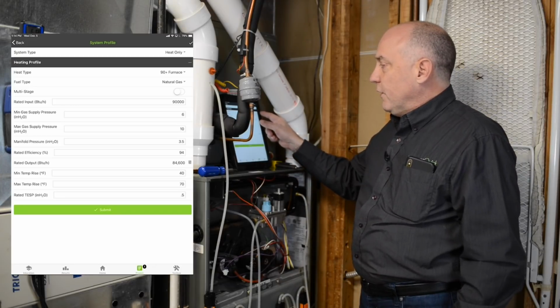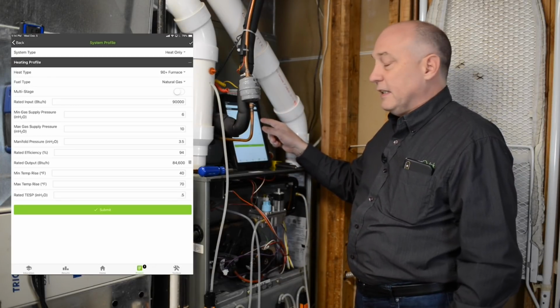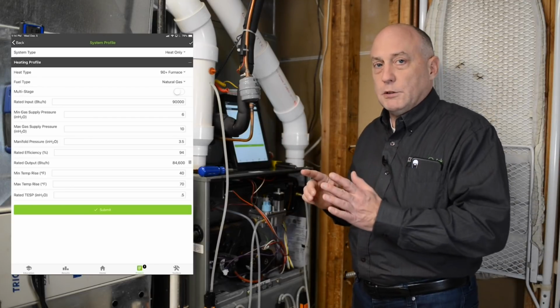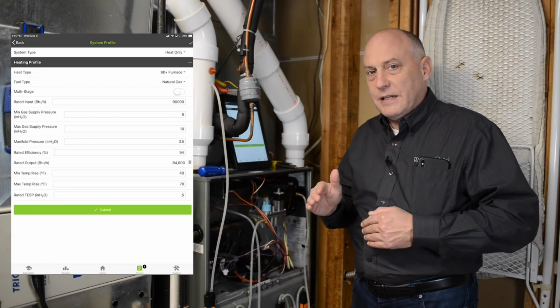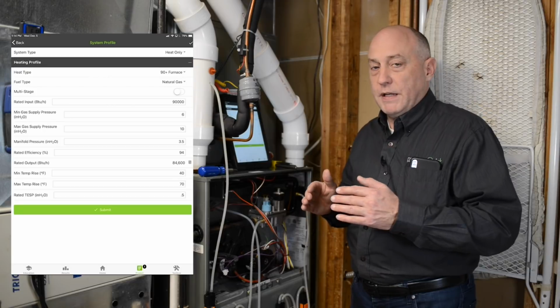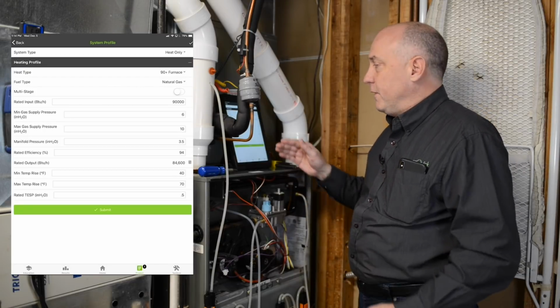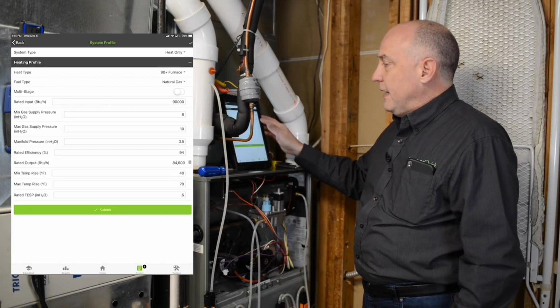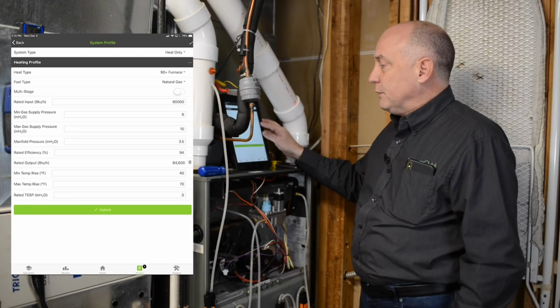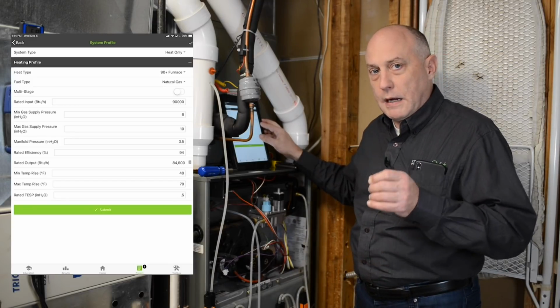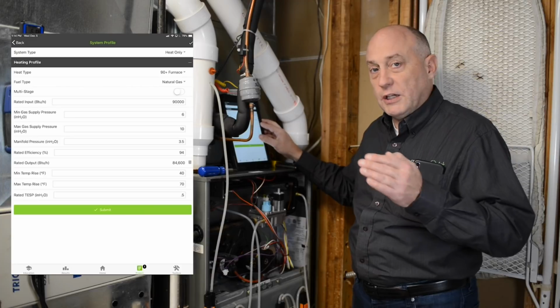So this is a 90+ furnace, natural gas. I'm just setting this up as a single stage. This is a fully variable speed furnace, but we're going to test it on high fire only because that's the only way you can test this type of unit. So my rated input's 90,000. I got my minimum supply gas pressure, that's 6 inches. That's the minimum allowable gas pressure for the regulator to adjust properly.